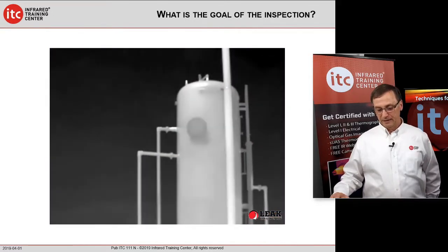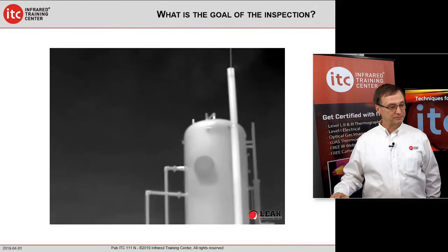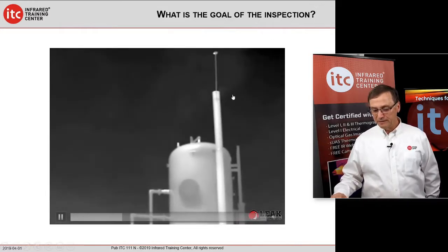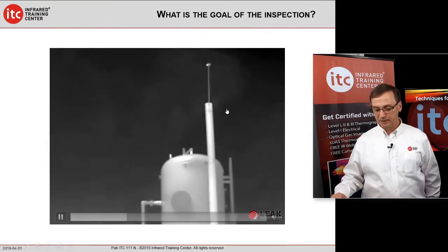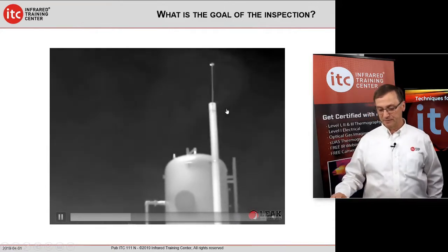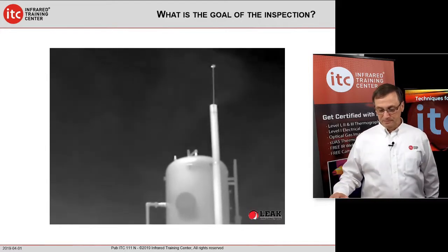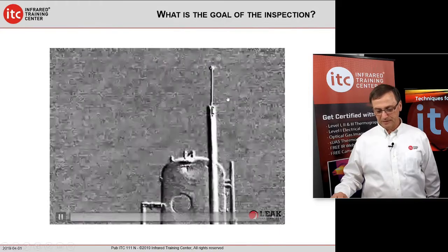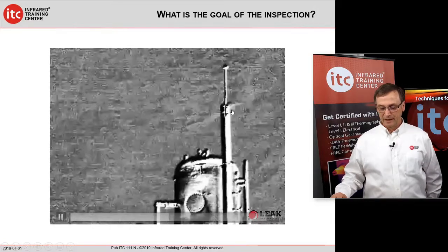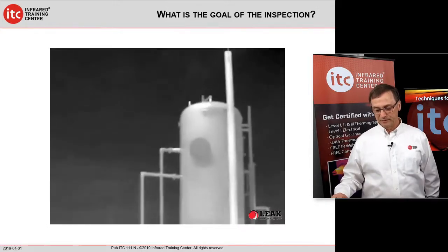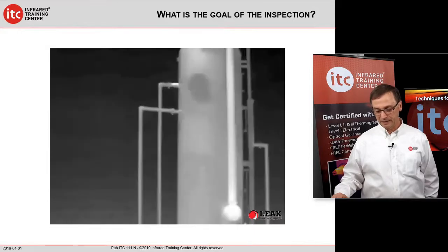and going into the auto, looking for leaks. I don't believe there was anything here. Maybe a little bit of gas coming up at the top here. We'll see that in HSM. I believe there is a leak up there. I can see that now. But this is just a good example of that. I'll advance this a little bit in the interest of time. And there's the high sensitivity mode, the HSM, indicating on that particular event, I believe, that there was a gas leak. Okay, so that'd be a good idea of a survey, just a survey, to get a big, broad idea of what you're dealing with.